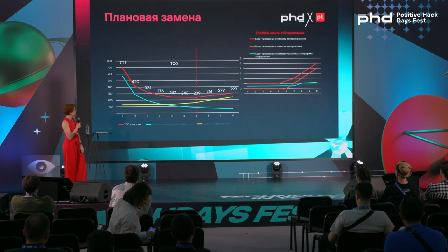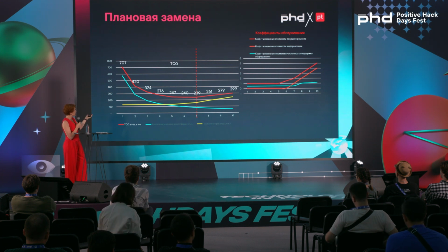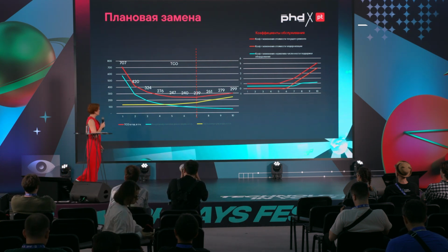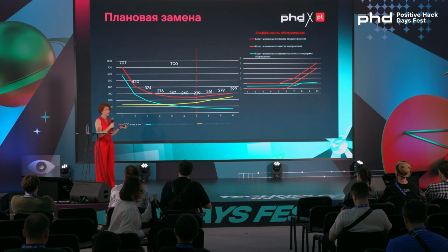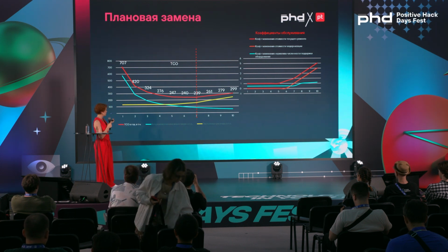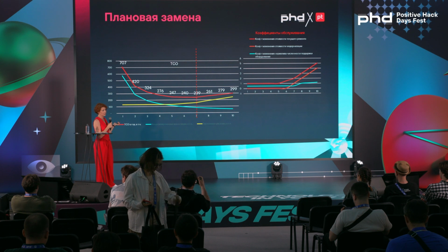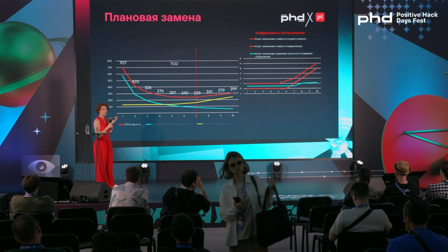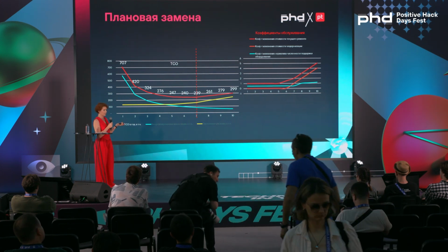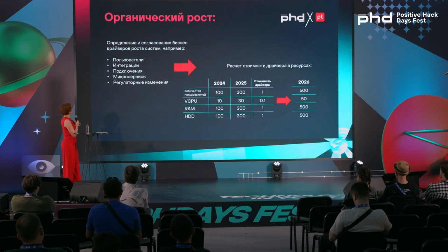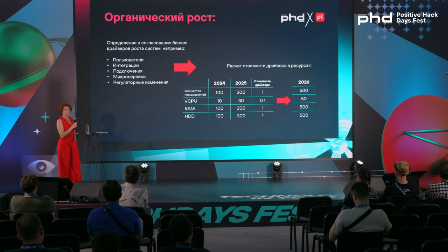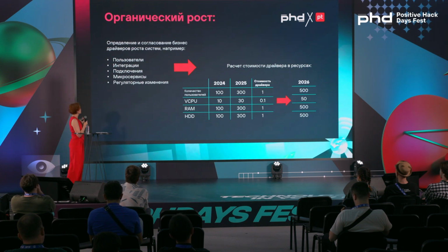And then we just spread the cost of the equipment over the span of 10 years. We see that the minimum cost of ownership is achieved at the level of 7 years. And actually, for virtually every piece of equipment installed in racks, we arrived at this horizon of 6 or 7 years. And now we don't really have these problems. It's become much easier for us to explain why we have set this replacement term.